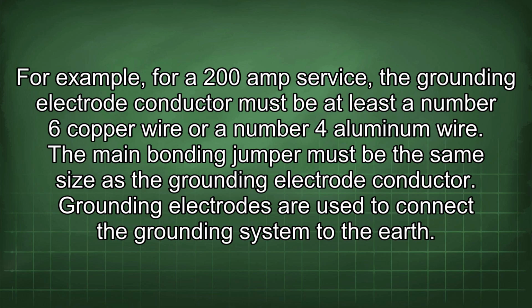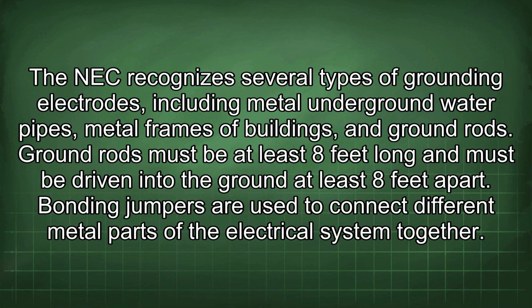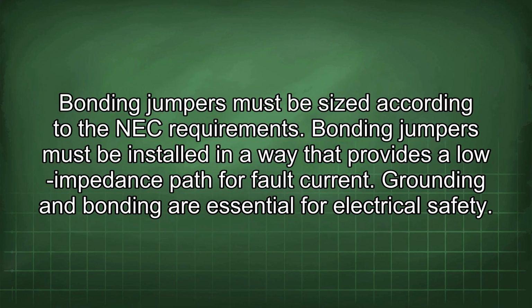Grounding electrodes are used to connect the grounding system to the earth. The NEC recognizes several types of grounding electrodes, including metal underground water pipes, metal frames of buildings, and ground rods. Ground rods must be at least 8 feet long and must be driven into the ground at least 8 feet apart. Bonding jumpers are used to connect different metal parts of the electrical system together. Bonding jumpers must be sized according to the NEC requirements. Bonding jumpers must be installed in a way that provides a low impedance path for fault current.